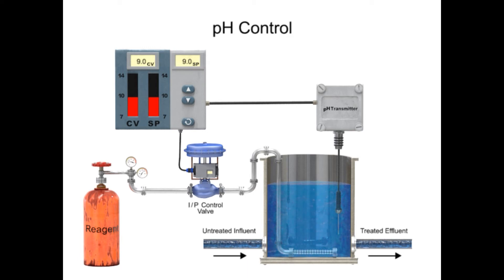An example of an automatic pH level control system is a water treatment process where lime softened water is maintained at a pH of 9 using carbon dioxide as a reagent.